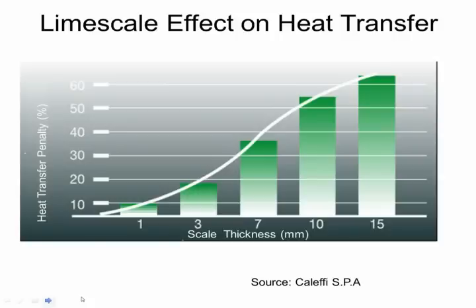Okay? So limescale is an insulator, and this next chart shows you an idea of the effect of the thickness of limescale in millimeters, and the penalty it has on the heat transfer ability of the heat exchanger. So as an example, we can see as little as 1 millimeter of limescale caked on some type of heat exchanger. This could be your chiller, it could be your boiler, it could be your otherwise heat exchanger. 1 millimeter can penalize you 10%. What does that mean? Well, if we have a 1 million BTU per hour delivery on our boiler capacity, we're now talking 900,000 BTUs per hour, 10%. I mean, I've talked to building managers that would give their pinky for 2%. So why give up 10% with just a 1 millimeter buildup?